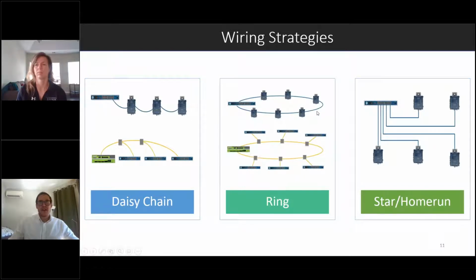So if I were to come and cut this cable right here, we could still have communication go out this direction for these 3 controllers and then come out this direction for these 3. So a physical break is able to be dealt with, so to speak, with this added redundancy with a ring. But there is a little bit more setup associated with that. So I mainly say to stick towards this if it's called for in a data center, but more often than not, a daisy chain strategy is going to be more than sufficient for any of your BAS designs.